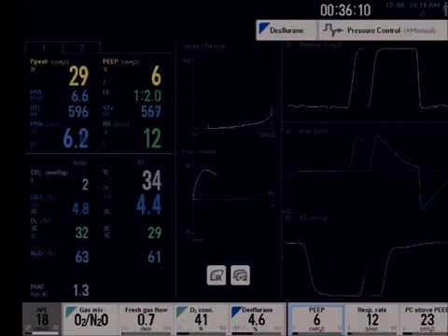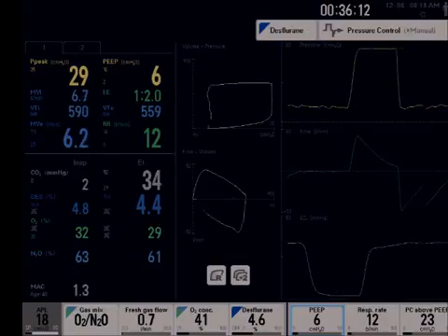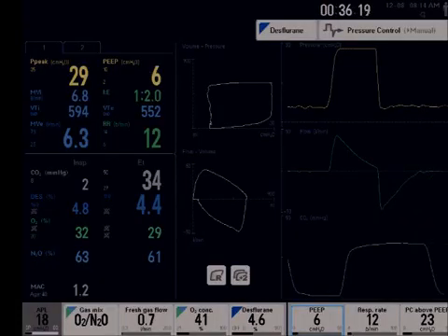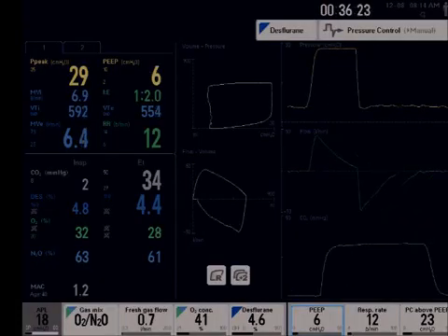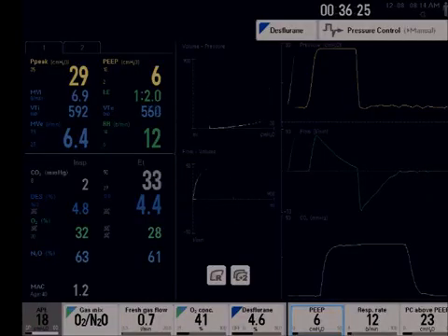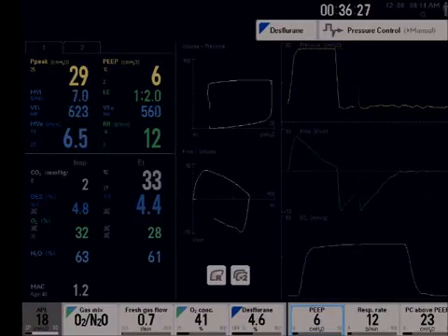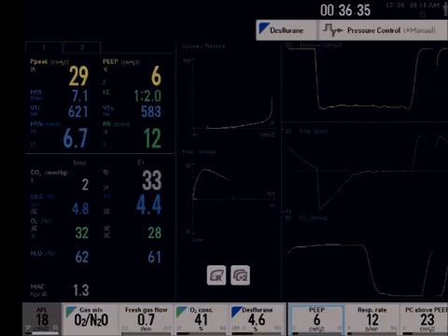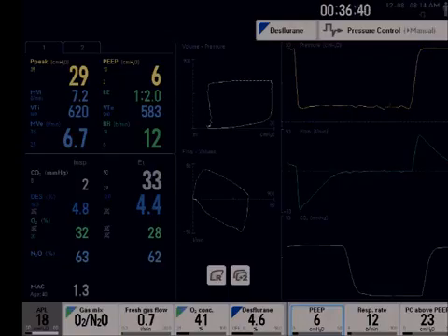Now this is actually a patient having laparoscopic surgery, and this is going to show the dramatic change in compliance and what happens during pressure controlled ventilation. The abdomen is currently inflated at this time, and with the pressure control of 23, my settings are at the bottom of the screen, you notice that we're getting an exhaled tidal volume of approximately 600 cc's.